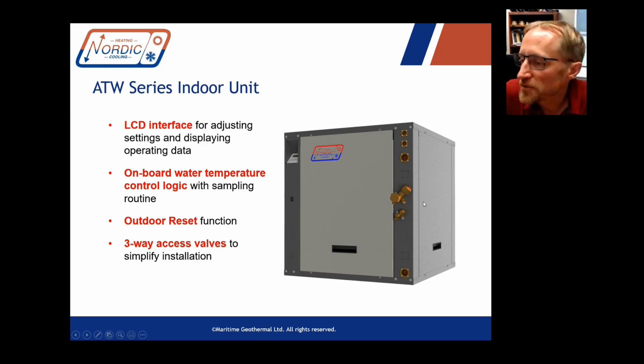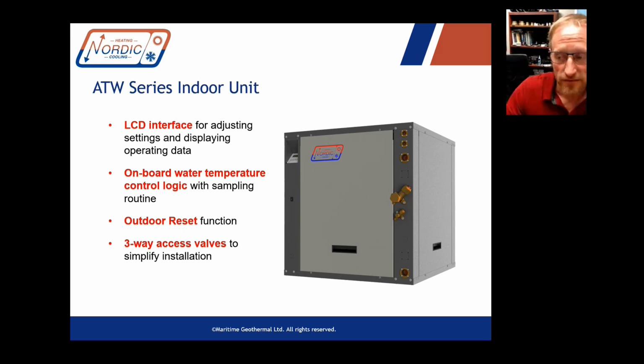Three-way access valves, you'll notice them here. They're just like on a mini split. So one of the disadvantages, I guess, of not having a monoblock system like our competitors is that refrigeration work needs to be done on site. But it's a very common expertise. There are a lot of service technicians around who know how to install mini splits, because there are so many mini splits put in every day that the same expertise is used to connect the indoor and outdoor units in this case.